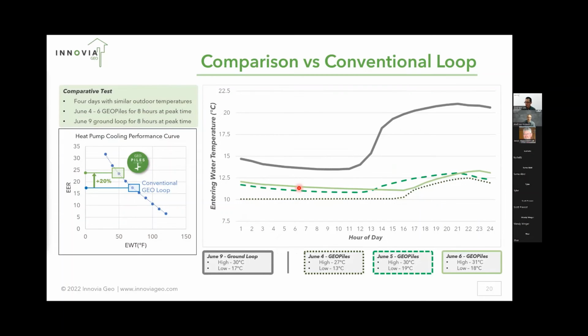And so these 3 lines here was the operation of the geopile system. And so we can see that the entering water temperature, we were able to keep that in a pretty tight range. So we were able to keep it, I think it was just less than, or maybe just over 13 degrees Celsius. So that was the range that we're able to operate the system at. With the conventional loop, when we turn the system on to maximum, what we can see here is that because the fluid volume in the system is substantially less, that temperature increases pretty quickly. And so it rises up pretty quickly, and then it leveled off and operated at about, I think it was about 21 degrees Celsius consistently at that steady operation stage. And so that's a pretty big difference.